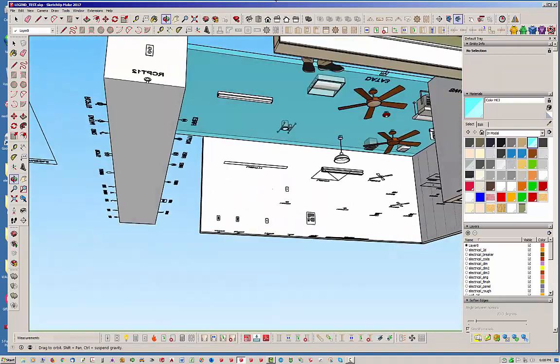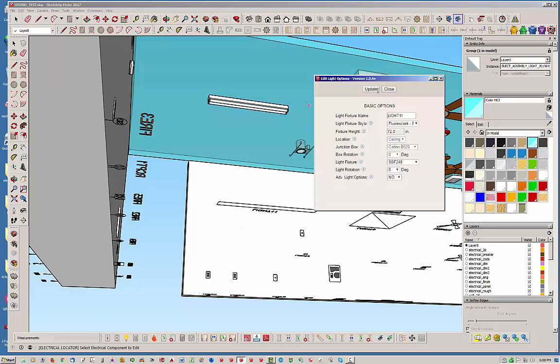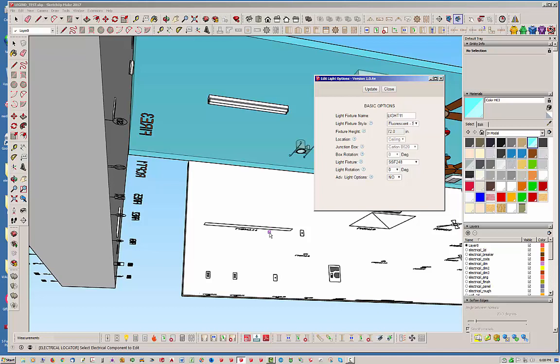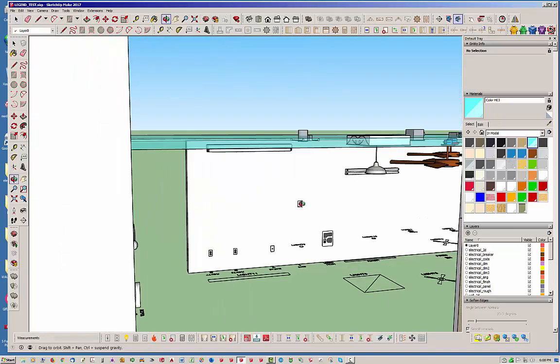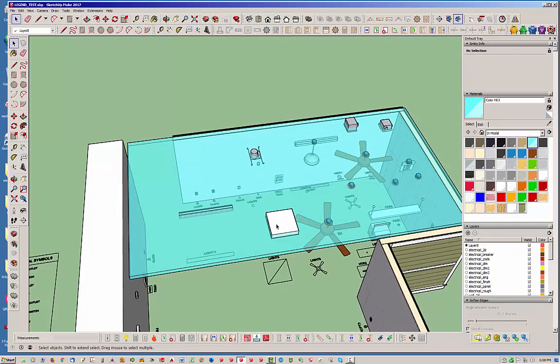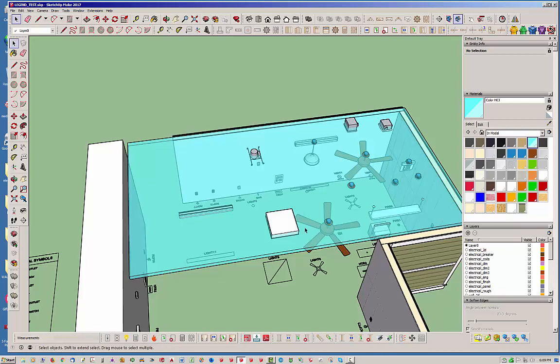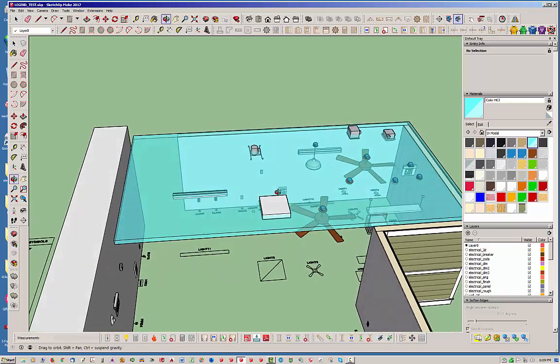Basically all you have to do is click this edit electrical button, select your item and hit update. And you'll notice it redrew the symbol below the fixture in the right spot. So it realigned it. That's basically what you need to do with ceiling fixtures. If you do decide to move them manually, well of course there really only is one way to move things with this plugin right now, manually with the native tools. So if you do move a ceiling fixture in the X Y plane or however, then you just need to regen it by editing it and hitting update and it will update the symbol as well.